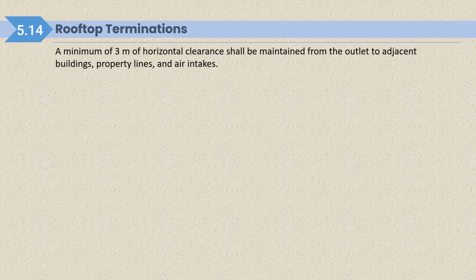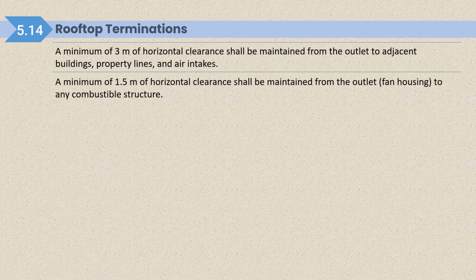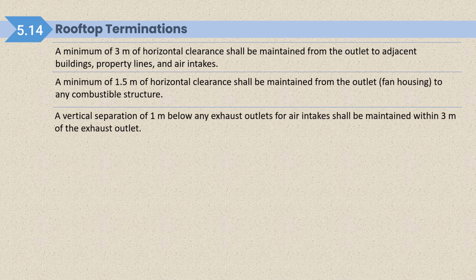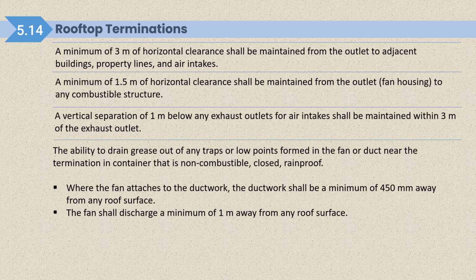Rooftop termination: a minimum of 3 meters of horizontal clearance shall be maintained from the outlet to adjacent buildings, property lines and air intakes. A minimum of 1.5 meters of horizontal clearance shall be maintained from the outlet fan housing to any combustible structure. A vertical separation of 1 meter below any exhaust outlet for air intake shall be maintained within 3 meters of the exhaust outlet. Grease shall be able to drain out of any tray or low point formed in the fan or duct near the termination into a container that is non-combustible, closed and rain-proof.